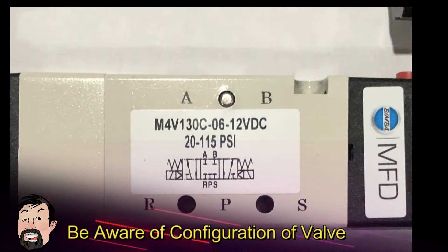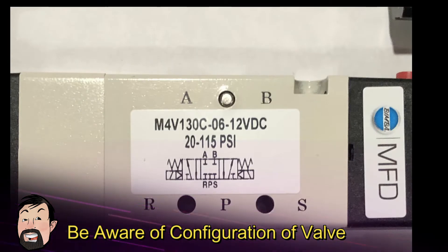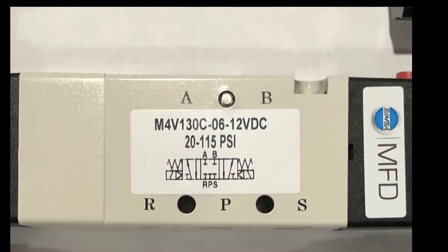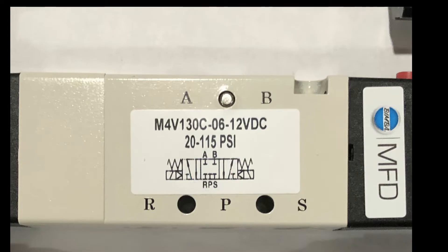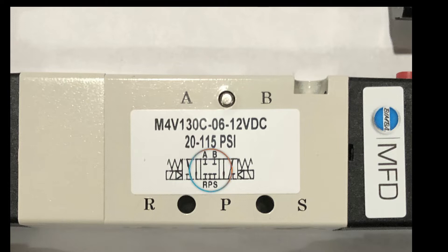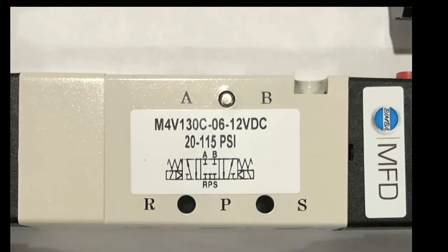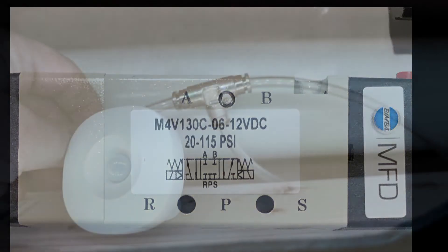So this is what you call the all ports block valve. The reason why it's called that, because if you take notice to the center position A, B, R, P and S, the air cannot go anywhere. This is by design. There's no air coming in and there's no air being released. It's just being held there. So that's the reason why I chose this valve. So if the power were to get shut down or whatever, the door would just stop.